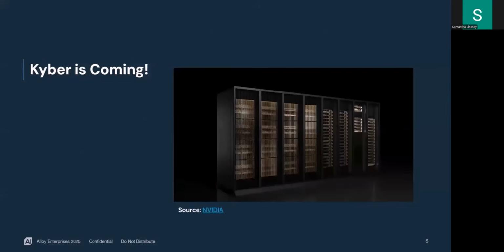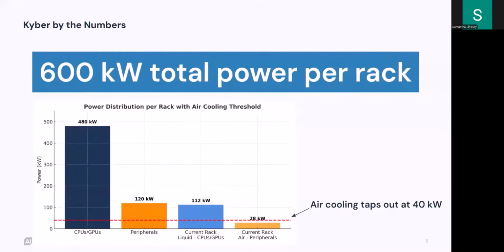So when you break that down, that's 600 kilowatts total power per rack, and using industry standard ratios, typically if you're cooling just the CPUs and GPUs in a system, you're capturing about 80% of the total heat load in the liquid loop, and the rest would need to be cooled by air. So today, in a system at around 120-ish kilowatts, if you're only cooling 80% of that, the remaining 20% is doable with air. And we've seen air systems typically tap out somewhere around 40 kilowatts of total heat load.